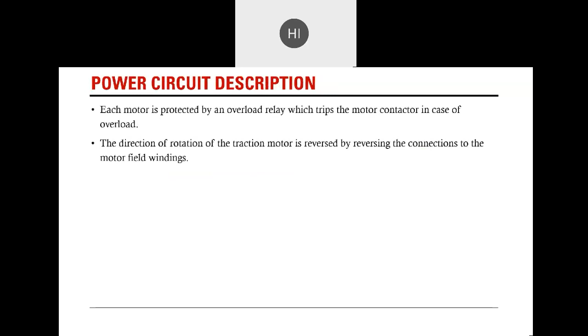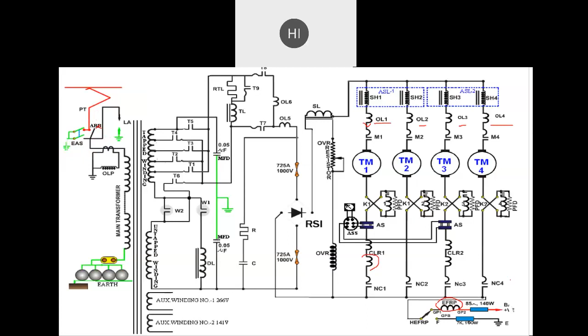Earth fault relay, it basically trips the VCB in the event of an earth fault occurring in any part of the motor circuit. So this earth fault relay, I'll go back again, this EFRP, this earth fault relay, this has been provided to trip the VCB. It is interlocked with this VCB. In case of any earth fault in any of the components, it trips the supply only, it trips. So we do not take any power only if any earth fault relay comes up.